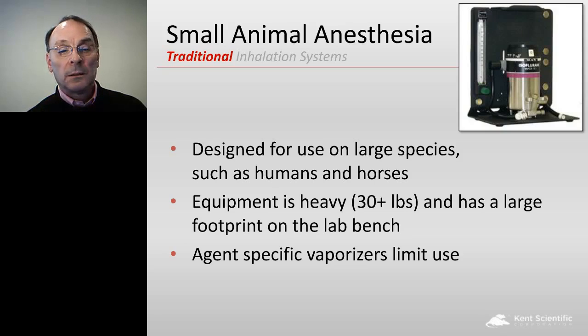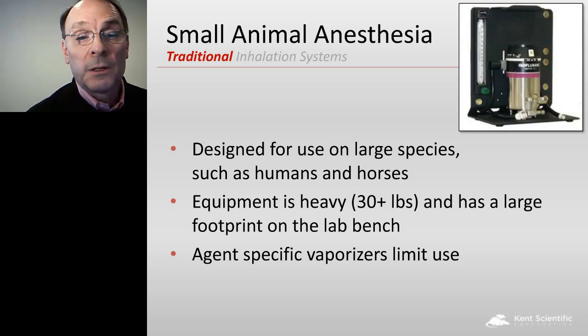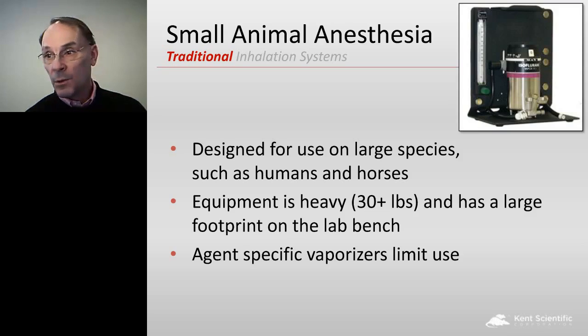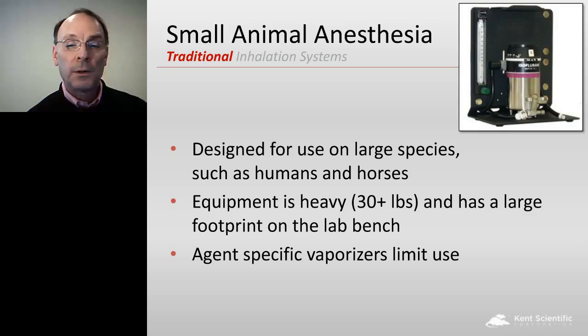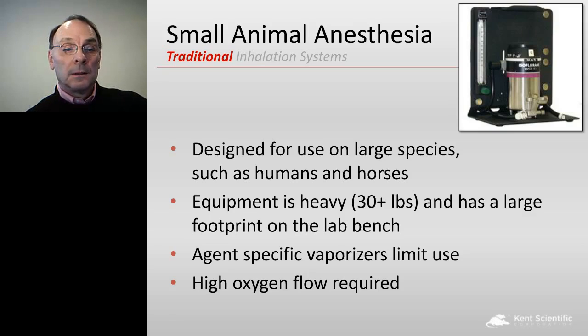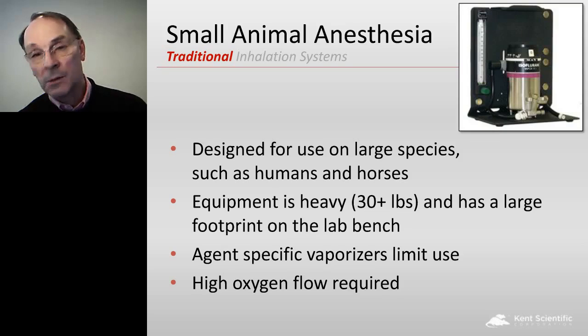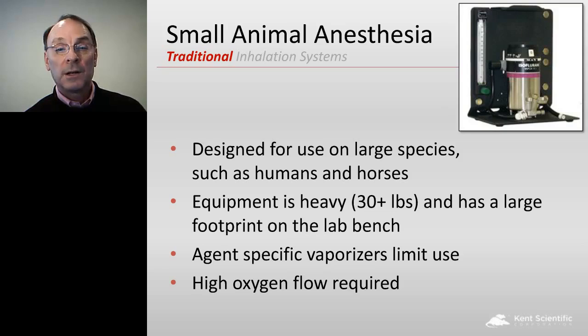And also the problem with typical vaporizers is that they are agent specific. So a halothane vaporizer, which people really don't use anymore, can't be used for anything else. If it can be retooled or reworked, it might be able to be used. But if you're using a sevoflurane vaporizer, it can't be used for isoflurane. And typically a high oxygen flow is required. I just had an inquiry come in just yesterday from England, in which, for anesthetizing a mouse, the researcher was using 2.5 liters of oxygen per minute at 2% isoflurane concentration. That's quite a bit of gas for a mouse.